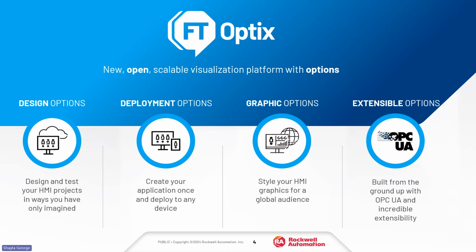Natively today it's not done natively, it's done through custom scripting. So Optix is an open API that allows you to do custom scripting using C#. So for MQTT, or if there are customizable features and functionalities that are not native to Optix, using C#, you can do that customization. But with MQTT, in one of the later releases, I believe it's 1.6, the MQTT protocol will become native. And so it won't require you to have to do that custom scripting.